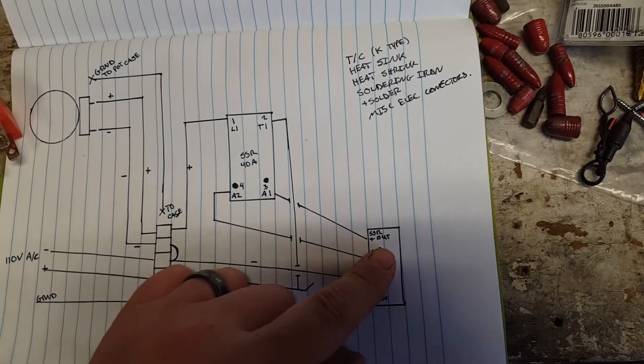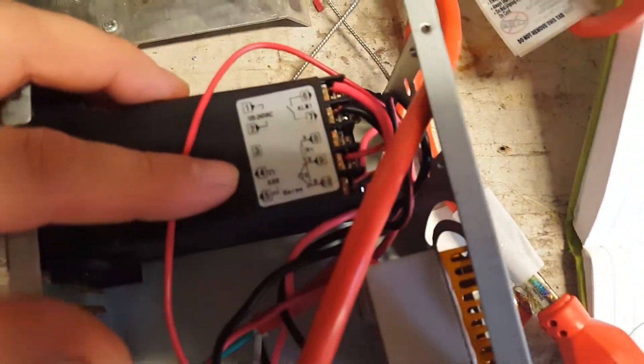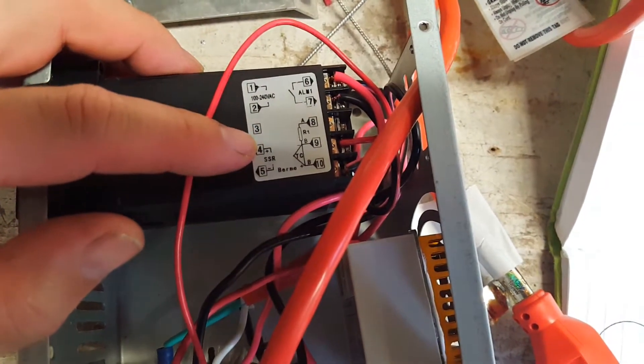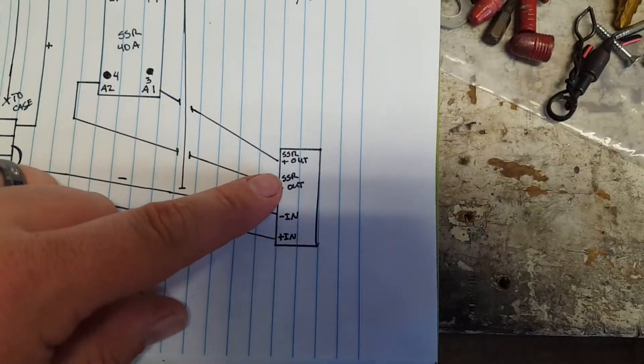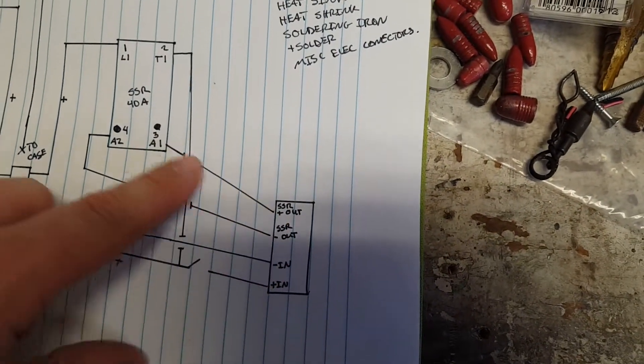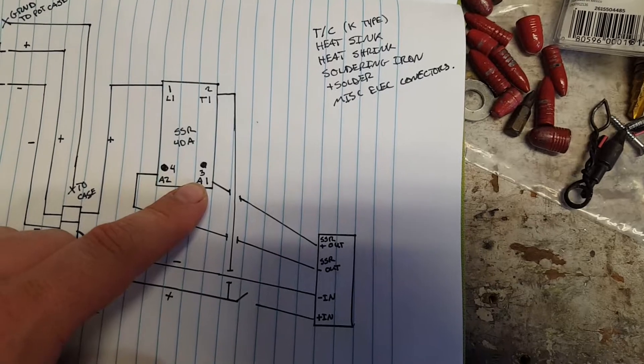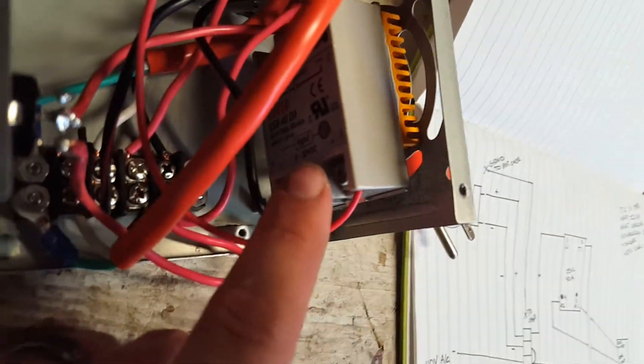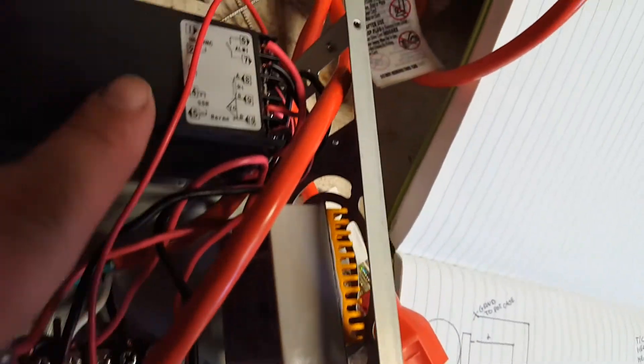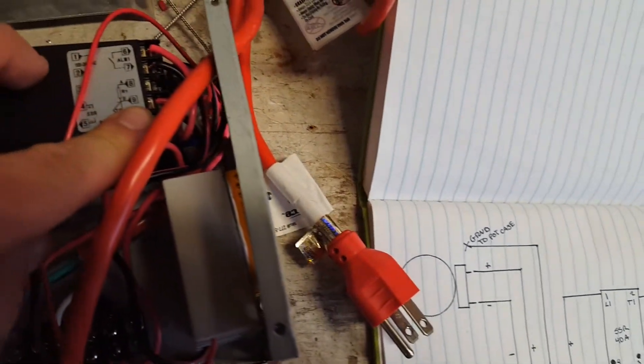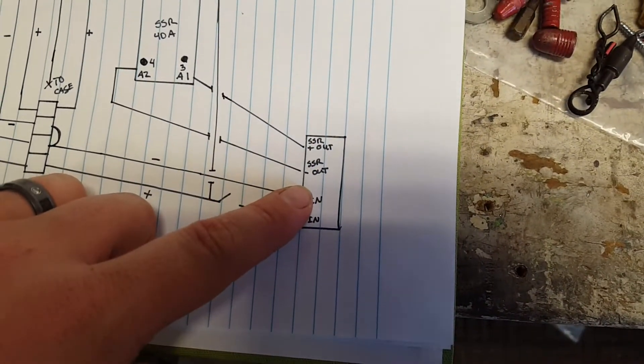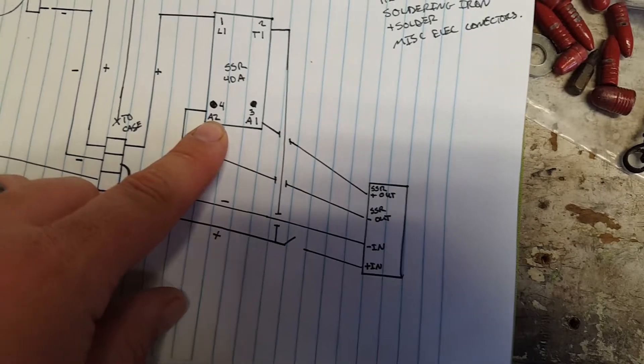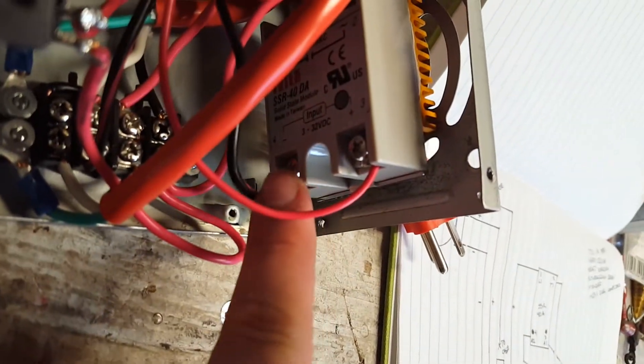Your PID controller should have markings or on the schematic somewhere for solid state relay positive and negative out, which is right here. So your solid state relay out comes up here to position three or A1 on your solid state relay, which is this guy right here. Your negative comes out to position four or A2, which is this guy - position four, A2, black wire comes up and hooks in right there.